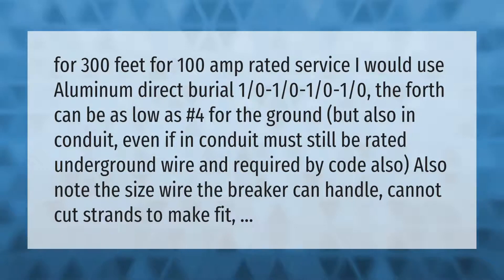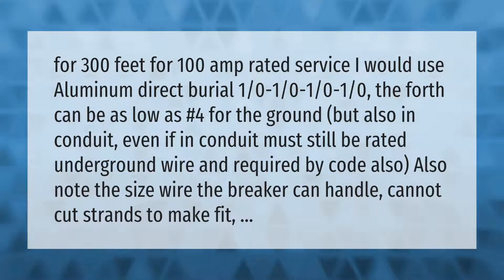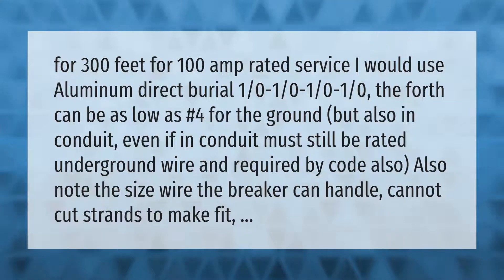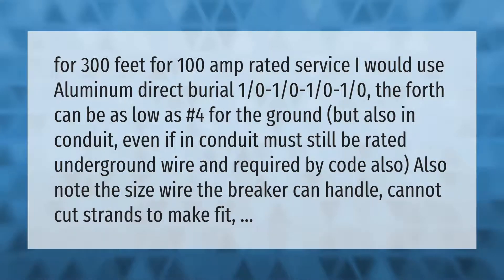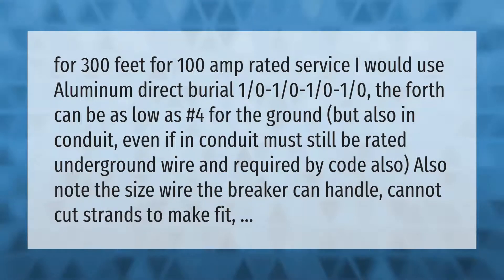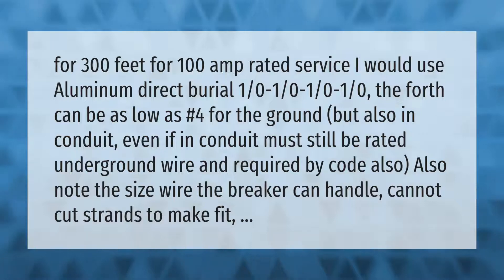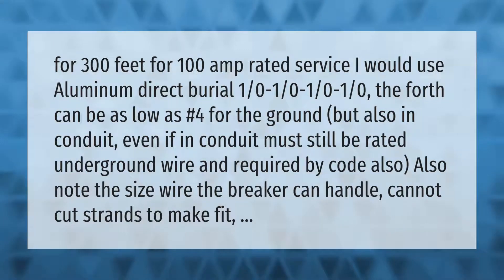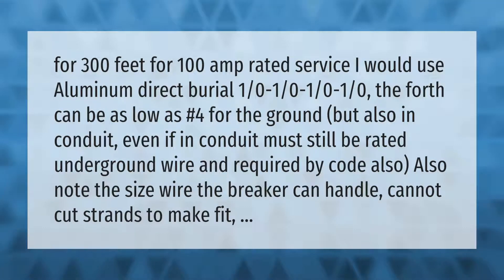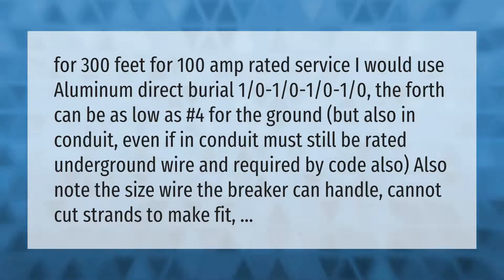For 300 feet of 100 amp rated service, I would use aluminum direct burial 1/0-1/0-1/0-1/0. The fourth wire can be as low as number 4 for the ground. Also, if in conduit, it must still be rated for underground wire as required by code. Note the wire size the breaker can handle — you cannot cut strands to make it fit.